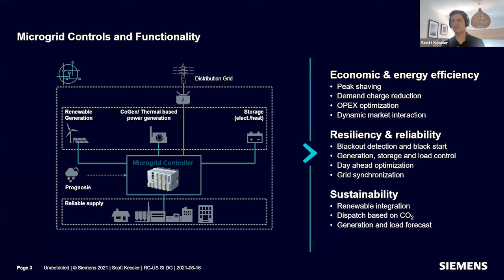Now some of the key functionality that emerges from a microgrid controller, you can see there on the right, I've bucketed into what I would see as the 3 main value propositions for microgrids. One being cost savings economics, and here a lot of the time, especially when you're looking at behind-the-meter microgrids, the focus can be on peak shaving, demand charge reduction, load shifting, actions that shave a lot of a customer's bill. That's where you see a majority of the opportunity coming from some of these microgrids.